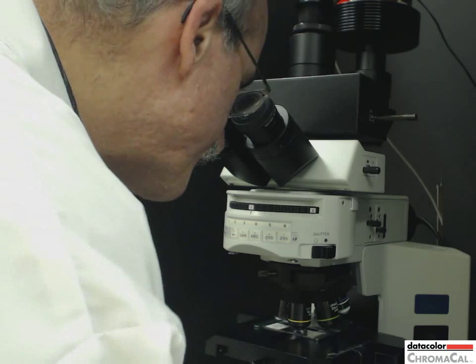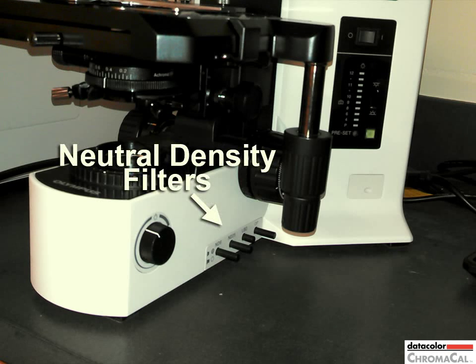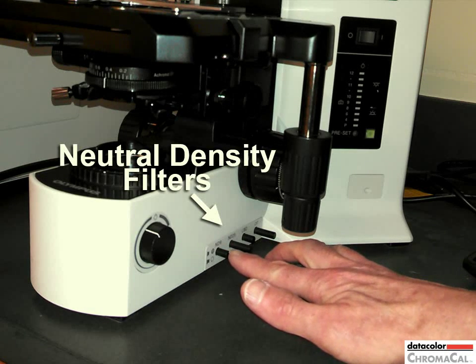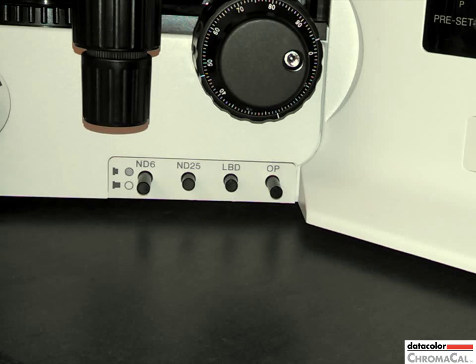If the lamp is too bright or too dark, move neutral density filters in or out of the light path. Here this is done by pressing a bar.